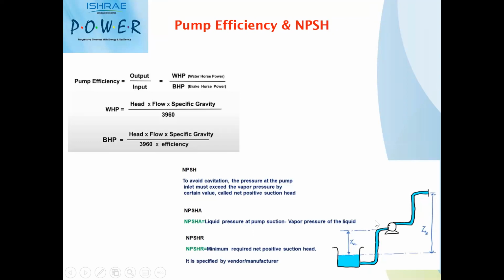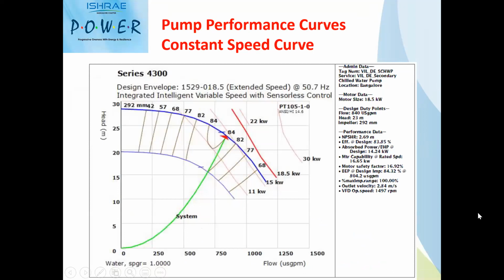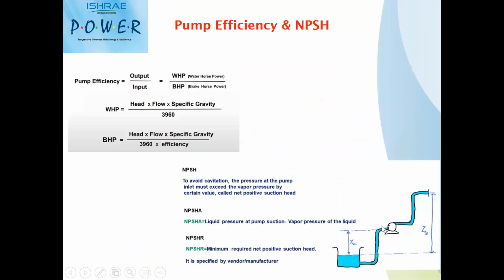Whenever we are designing the pump, the particular NPSH value is typically tested when we are prototyping and testing the pumps at the design stage and drawing these curves. For any particular pump, I'll go back to my previous slide. You can see here the value NPSH-R is 2.69. For that particular duty of 840 USGPM at 23 meters head, the net positive suction head required by this particular selected pump is 2.69, meaning you should have 2.69 as a minimum pressure available on the suction side of the pump to have smooth operation. So this is NPSH-R, which is a design parameter of the pump.